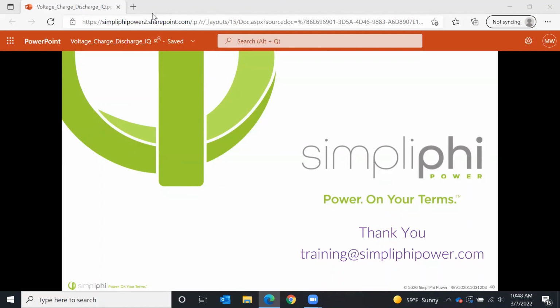Have you gone through UL 9540A testing for higher capacities and closer spacing than what is in NFPA 855? Yeah, actually we have. We've got a UL 9540A test report completed, and we're able to provide it to whoever needs it, your jurisdiction inspector or whoever needs it, we can send it over to them. It does allow for closer spacing. I don't remember exactly what that spacing is, and there's a lot of specifics about which side you're on, rear, front, etc.